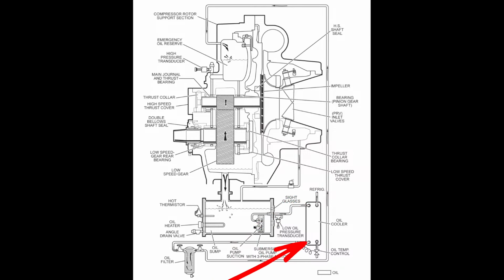So one way to tell that is just, is it actually opening? You can check your leaving temperature line to see what that looks like, because this will feed just back into the evaporator shell. It just has a port where the suction gas or the flash gas, whatever's coming out of the oil cooler, is just returning back to the evaporator. So you can take a measurement of that. Is this heat exchanger even just functioning? Are we feeding enough refrigerant into it? That could be the next issue itself. Maybe even if you're feeding proper subcooled liquid to it, doesn't mean that it's actually opening and controlling properly, which again, at high loads, when we need it to open, if it's stuck at a more closed position, then it may work perfectly fine at lower loads.